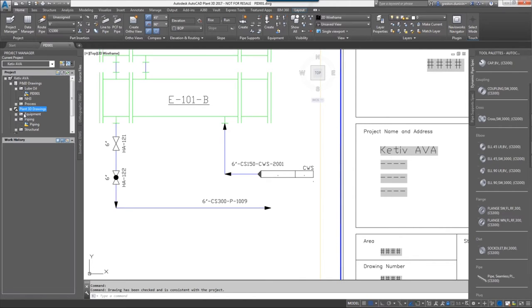Now, when we get down into Plant 3D, what I like to recommend to people is to separate things by discipline and service. So we'll have some drawings that are specifically for equipment and being laid out in a facility. We'll have a piping drawing that'll only have piping inside of it with the other folders XREFed in. I'll always recommend people use XREFs because that way you get the latest versions of the files. If somebody modifies anything inside the project, you'll know exactly what they're trying to do using the XREF functionality.